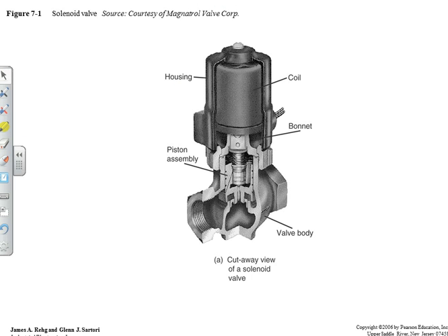Okay, Chapter 7 starts off with solenoid valves. Valves can push water, they can have oil go through them, they can have air go through them. I have some coil that turns it on. Normally a solenoid valve is going to be on or it's going to be off. It's not an in-between throttle type valve. The mechanical guys are normally in charge of the mechanical part of the valve. You as a technician would be in charge of the electrical part of the valve.